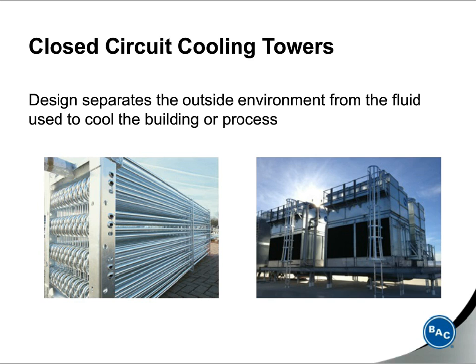Since the tower is recirculating the water over the serpentine coil, what's happening to all the dirt and debris that normally enters the system? Well, instead, it's being collected in the tower's collection basin. There's a strainer in the basin that prevents the dirt and debris from continuing to be recirculated. And the closed process loop that's basically contained within the coil prevents the dirt and debris from entering the rest of the HVAC system.